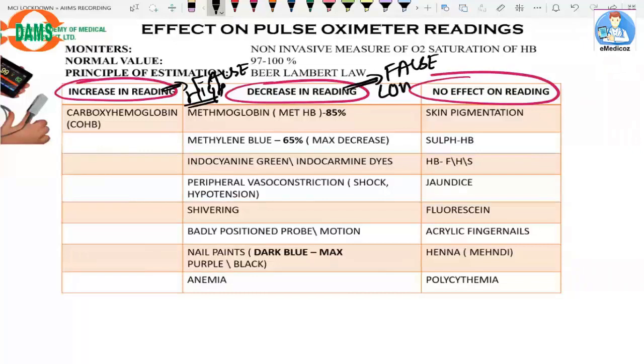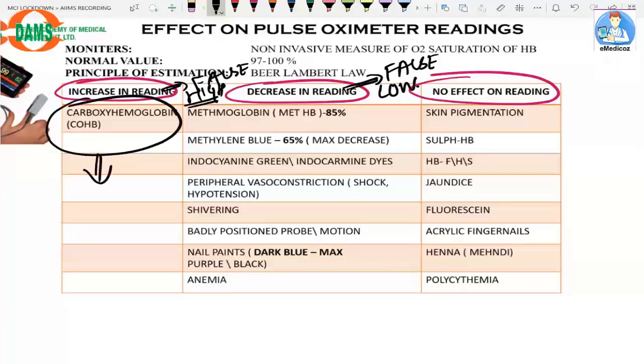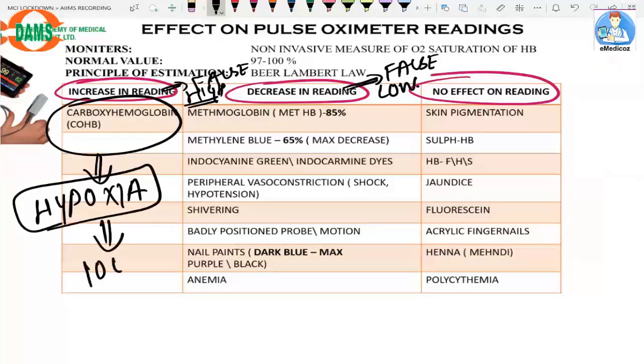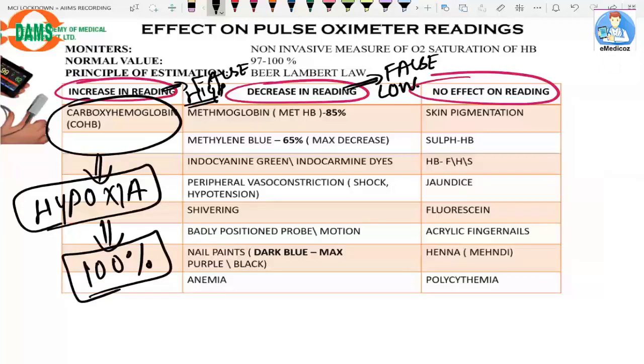Fortunately, there is only one example of a false high reading: carboxy hemoglobin (COHb). This causes an increase in the reading, meaning the actual O2 saturation is less and the patient has hypoxia, but what you see on the pulse oximeter monitor is 100% saturation.